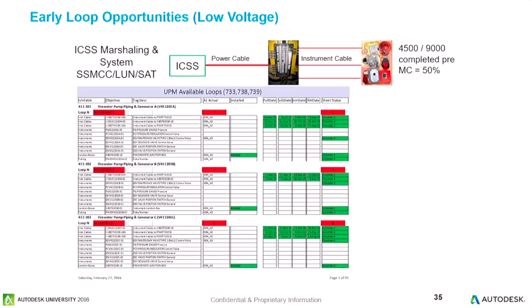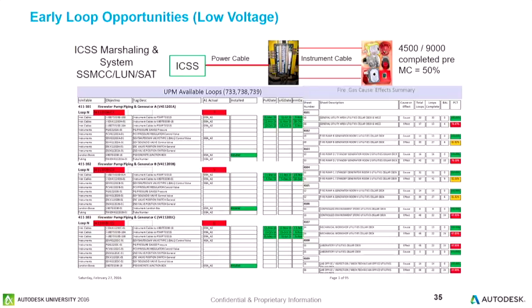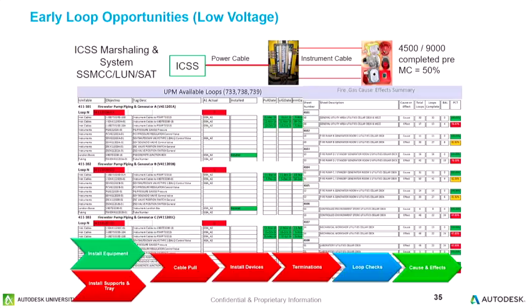It just doesn't happen. We went one step further into dynamic commissioning, saying now we have all this loop information, what are the loops associated with cause and effects, and can we get after these earlier from dynamic commissioning? So we'd gone from being effectively blind on E&I scope, other than the panels in the rooms, to creating clear visibility throughout the process, driving performance all the way to cause and effects.